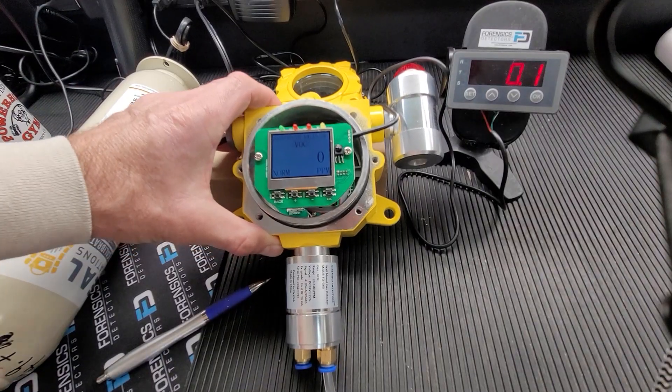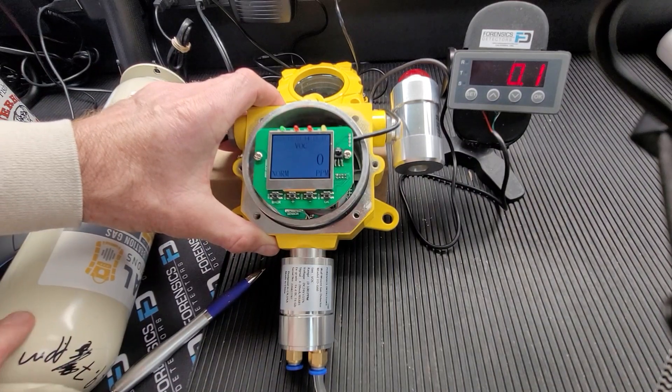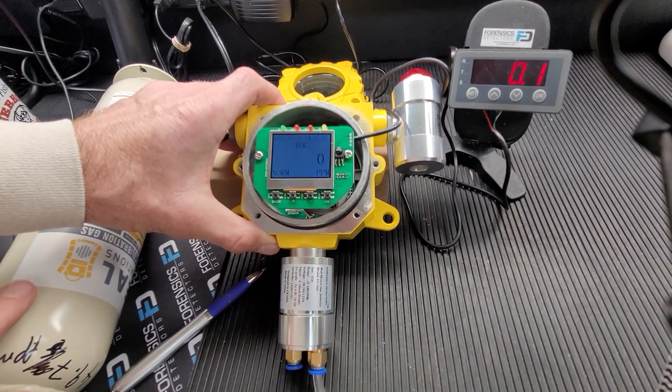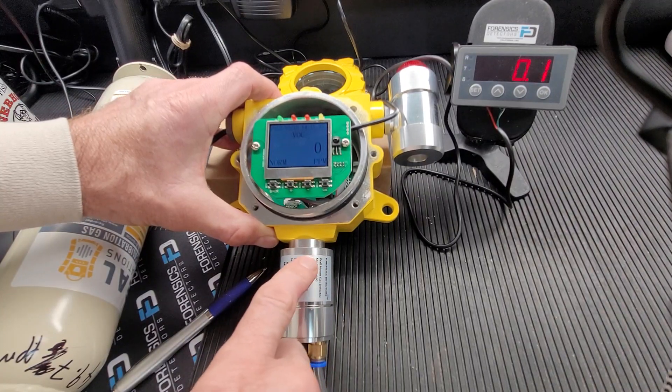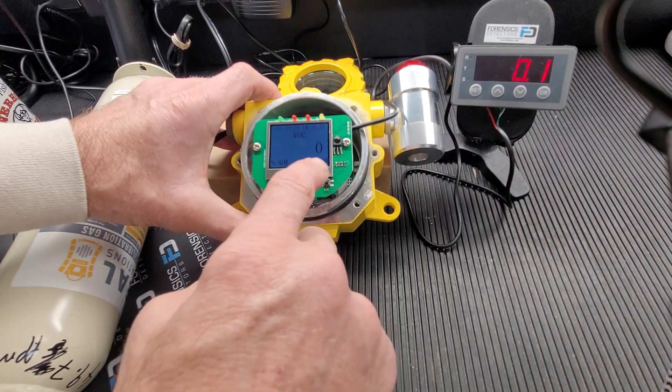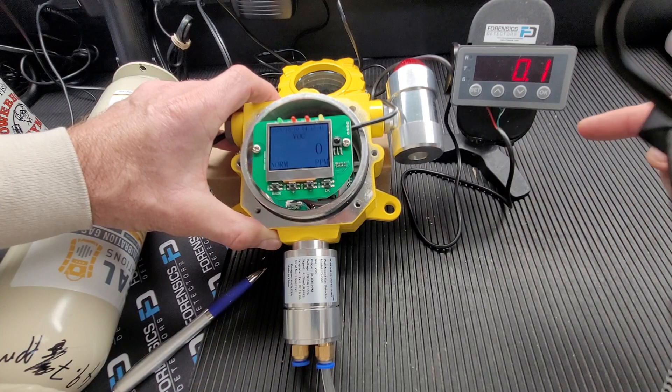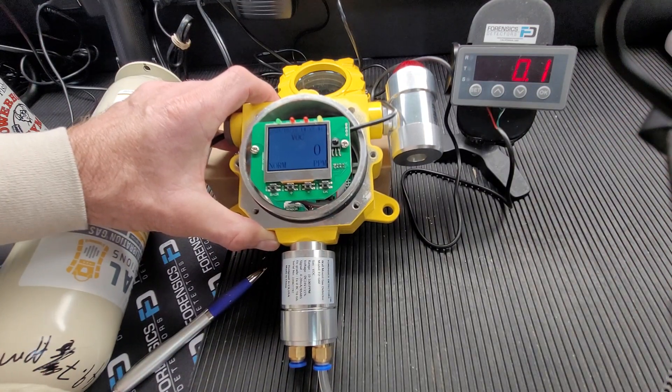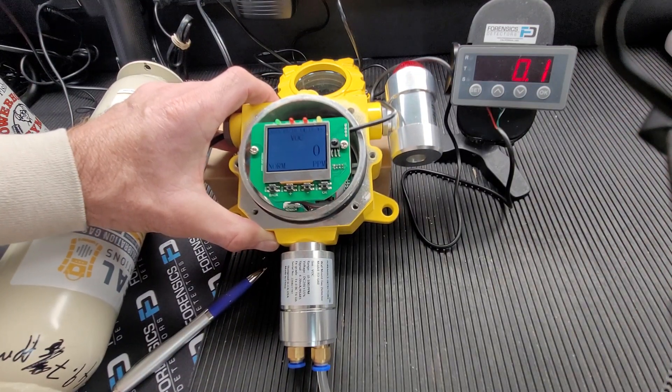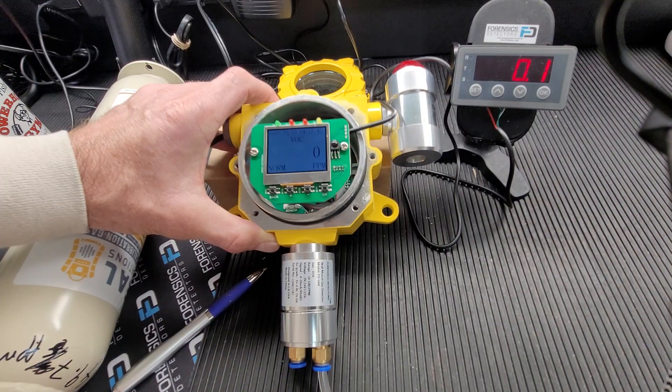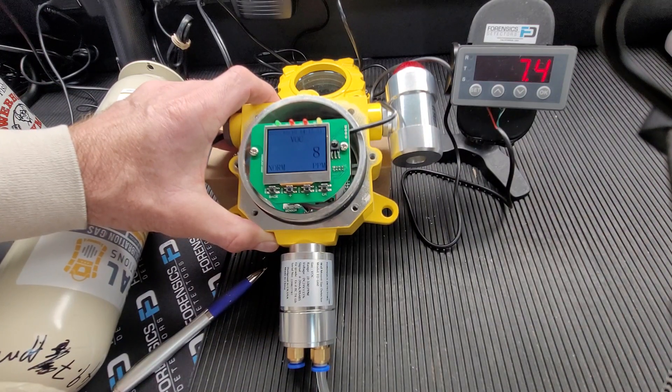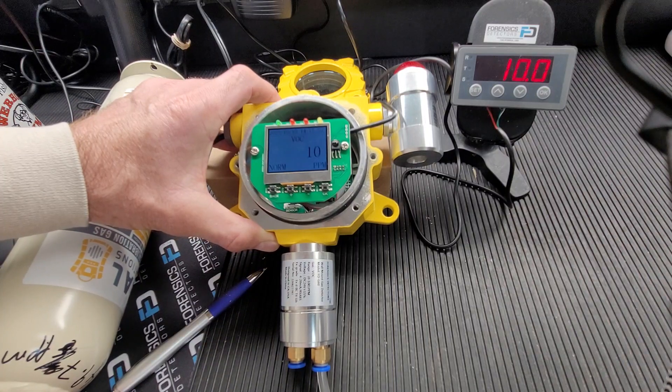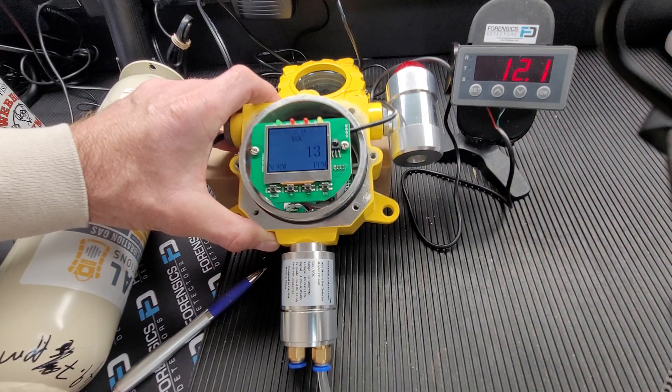So as you can see, we have a gas calibration bottle, isobutylene for VOC. It's connected to the calibration cap and straight onto the sensor head. As this increases, you will see a corresponding increase on the external 4 to 20 milliamp display. Let's pop in some gas. There it goes, and it tracks each other one-to-one. It's a beautiful setup. Very straightforward.